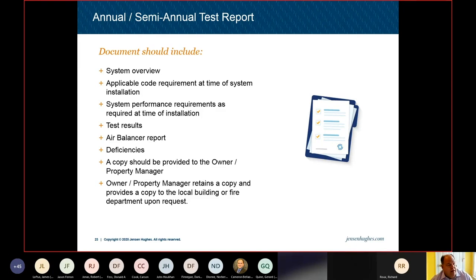Your overall test results, the air balance reports showing the performance of the mechanical systems, the deficiencies that are brought up, and a copy is provided to the owner and property manager, right? That owner or property manager then retains a copy and provides a copy to the local building or fire department upon their request. So if you're a local building or fire official and there's an addition or a renovation happening in the building, they might say, hey, give me all your semi-annual and annual testing for all your fire and life safety systems, including smoke control, as an example.